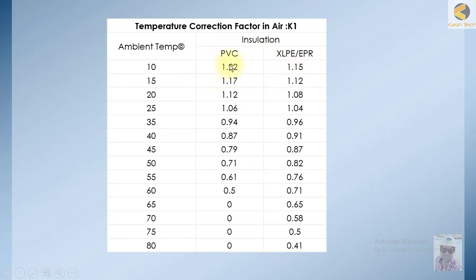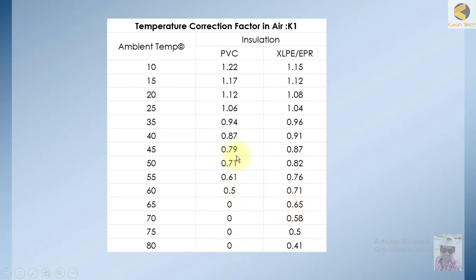An interesting thing here is that the PVC rating factor or K factor is more than XLPE because PVC can bear more temperatures. As the ambient temperature where the cable is laid increases, the K factor or rating factor that you multiply with the cable rating is also decreasing. After 65 degrees, it is not available to use PVC, whereas XLPE can be used up to extreme temperatures of 80 degrees. So PVC is preferable at lower temperatures. This is the example of the temperature correction factor K1.